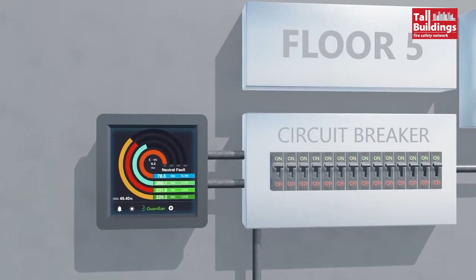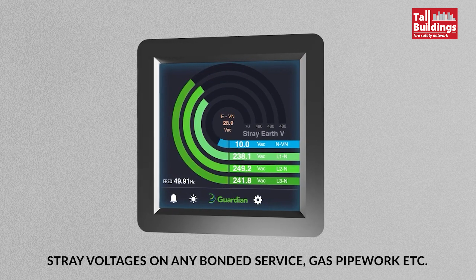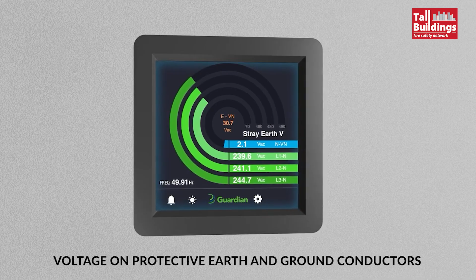With the Guardian monitoring in place and connected to this fuse board, an early warning would be sent to the building management company or owner as this fault was happening, and an electrician could be sent to repair the fault before it became a danger. The Guardian can also isolate the specific supply to that fuse board if the situation is becoming unsafe. The Guardian incorporates the patented OPEN technology and can detect faults including loss of neutral, broken PEN conductor, stray voltages on any bonded service including gas pipework, voltage on protective earth and ground conductors, high and low line voltages, and high and low frequency.